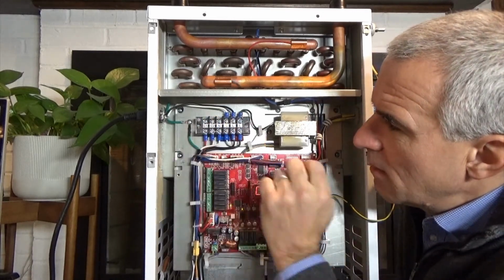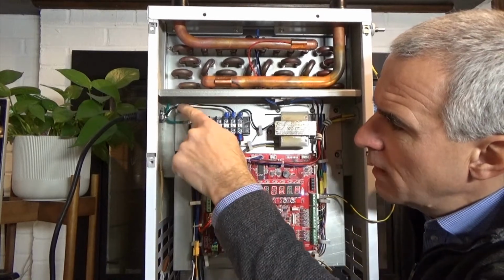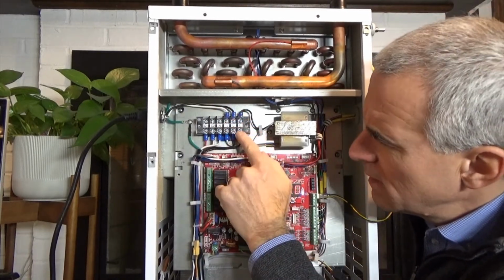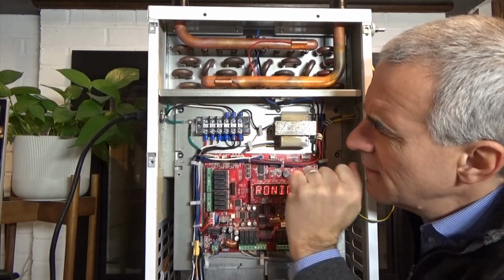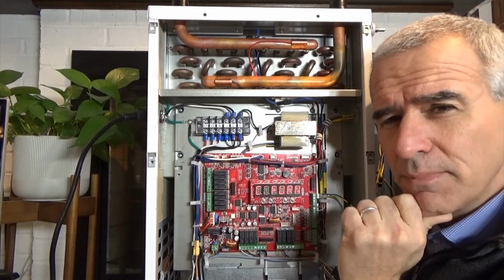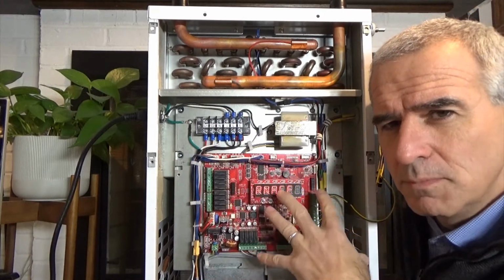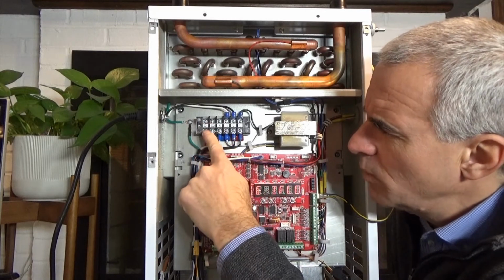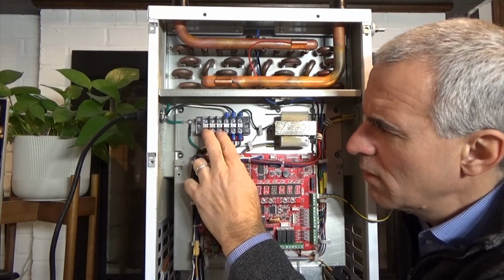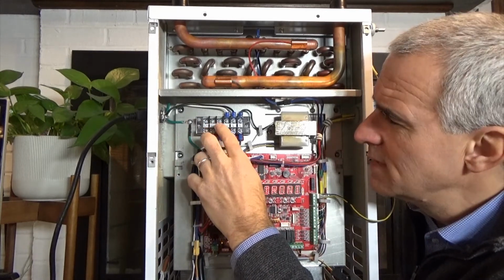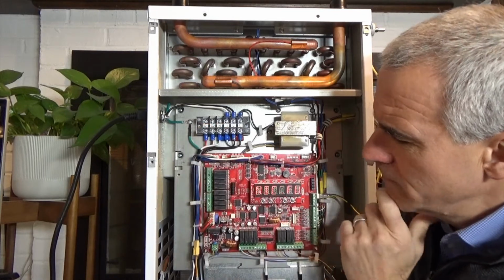Above, we have our power wiring. We're bringing our 120 volts into the unit at L and N here. We are driving the pump. We have onboard variable speed pump control that we will power from the C1 and N contacts here on the power strip.